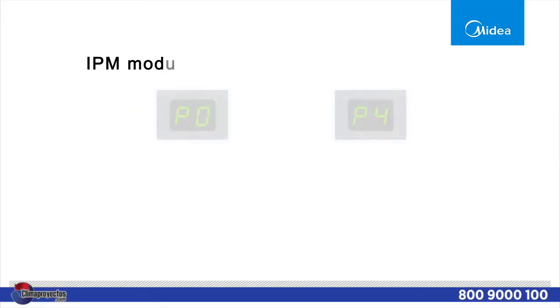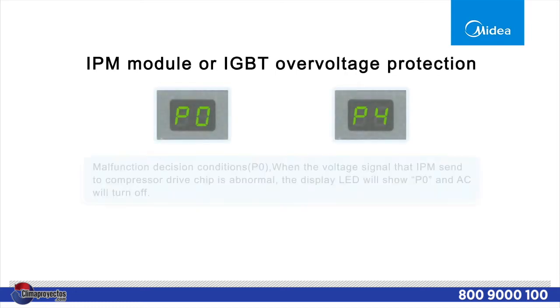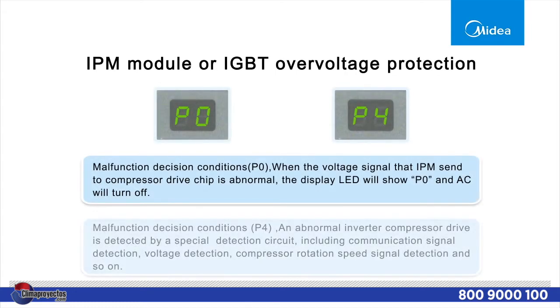When the indoor unit displays P0 or P4, that indicates an IPM module fault or IGBT over voltage protection.